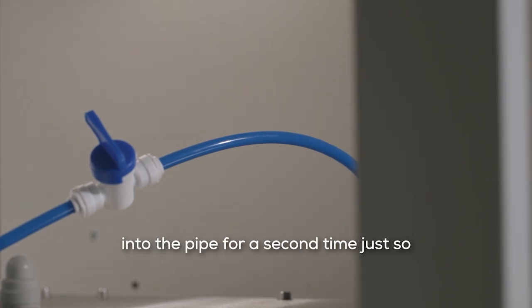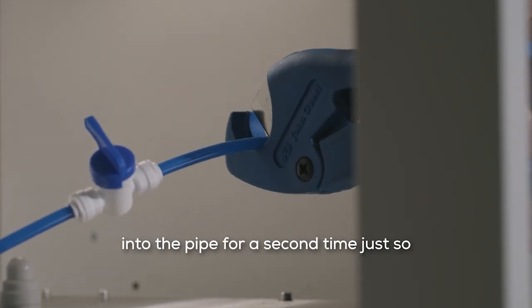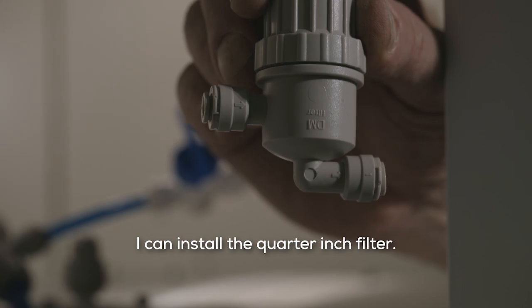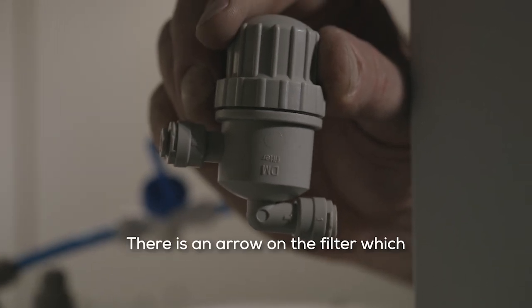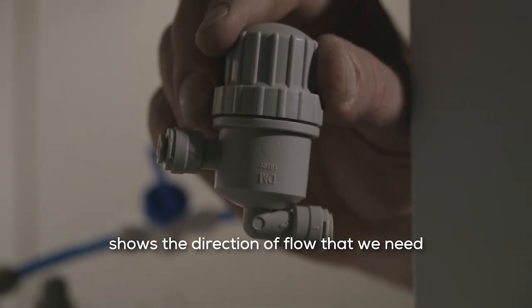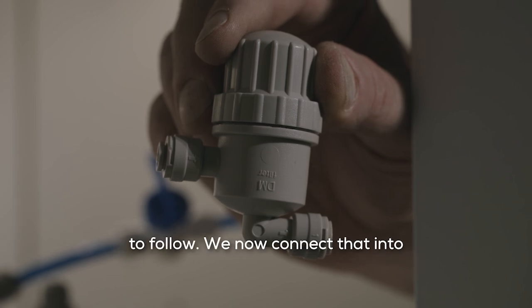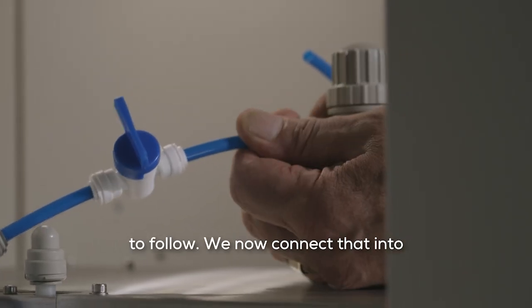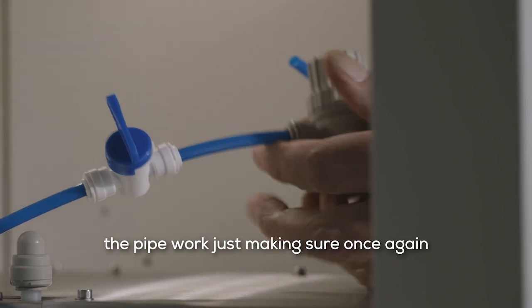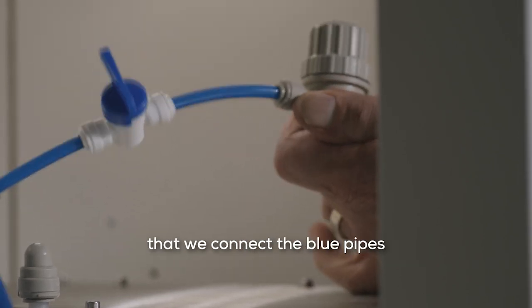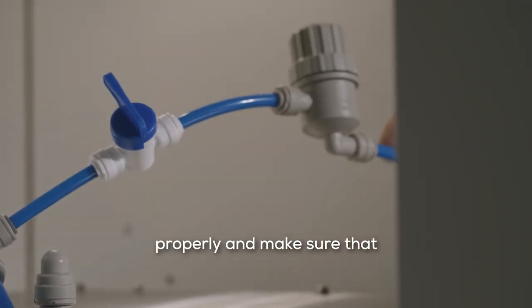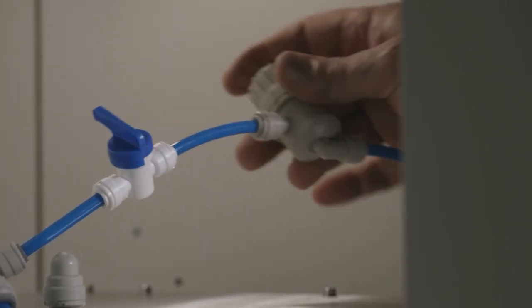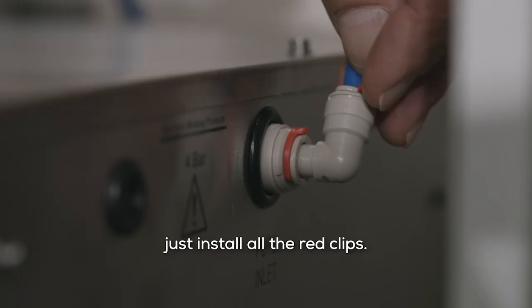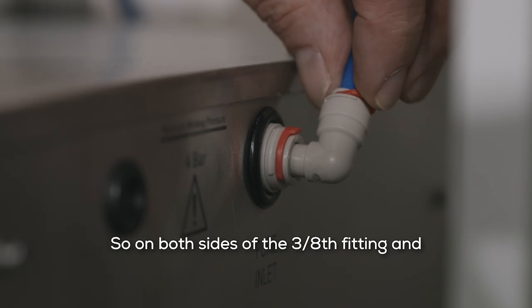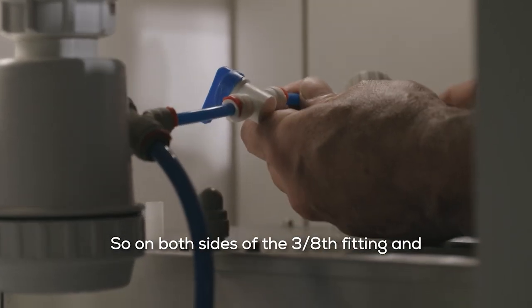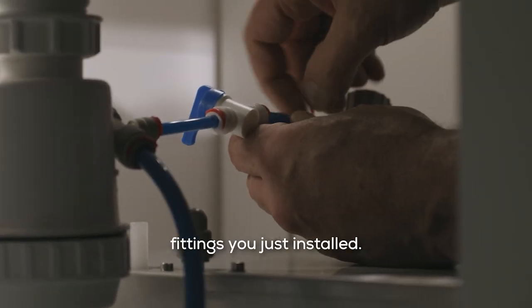I'm now going to cut into the pipe for a second time, just so I can install the 1/4 inch filter. There is an arrow on the filter which shows the direction of flow that we need to follow. We now connect that into the pipework, just making sure once again that we connect the blue pipes properly and make sure that that collar actually comes out. It's a good time now to just install the red clips, so on both sides of the 3/8 fitting and on all the 1/4 fittings you just installed.